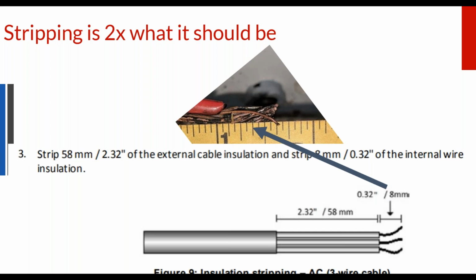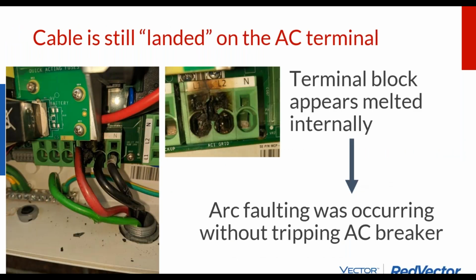So in this case, we were able to look at the conductor and measure it. And here we have the instruction manual calling for stripping to 1/3 of an inch. The instruction manuals say strip to 1/3 of an inch, and the installer stripped to about 5/8 of an inch. So they took off nearly 2/3 additional material beyond what the manufacturer was calling for. And because these two wires were stripped too long, when you plug them into that inverter, they get an arc and it burns up the terminal block.